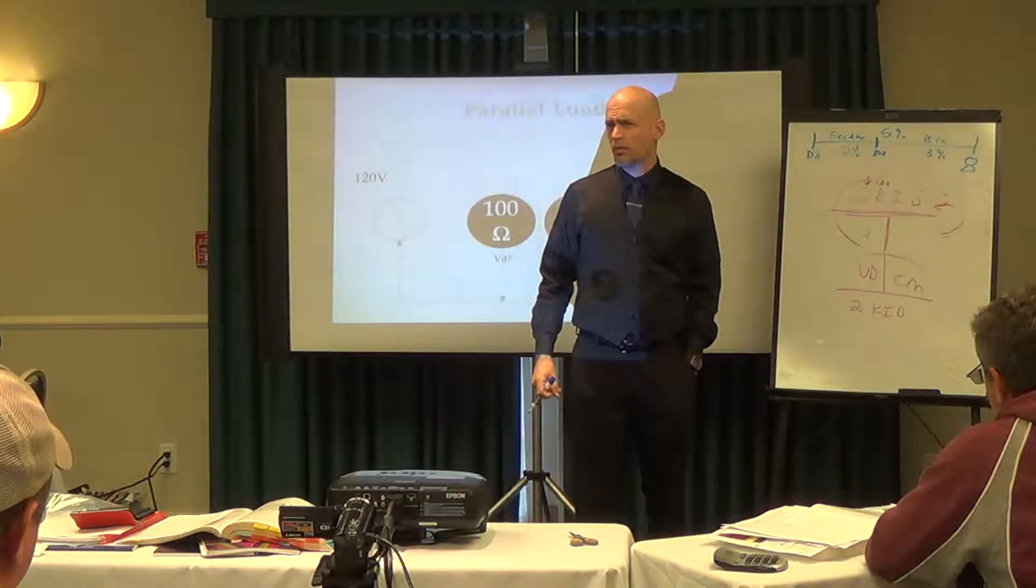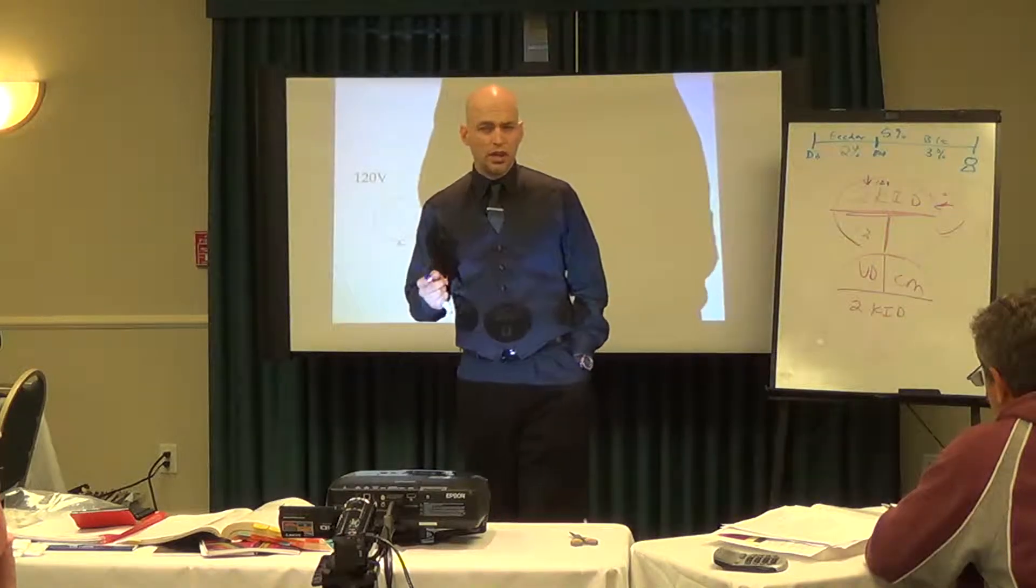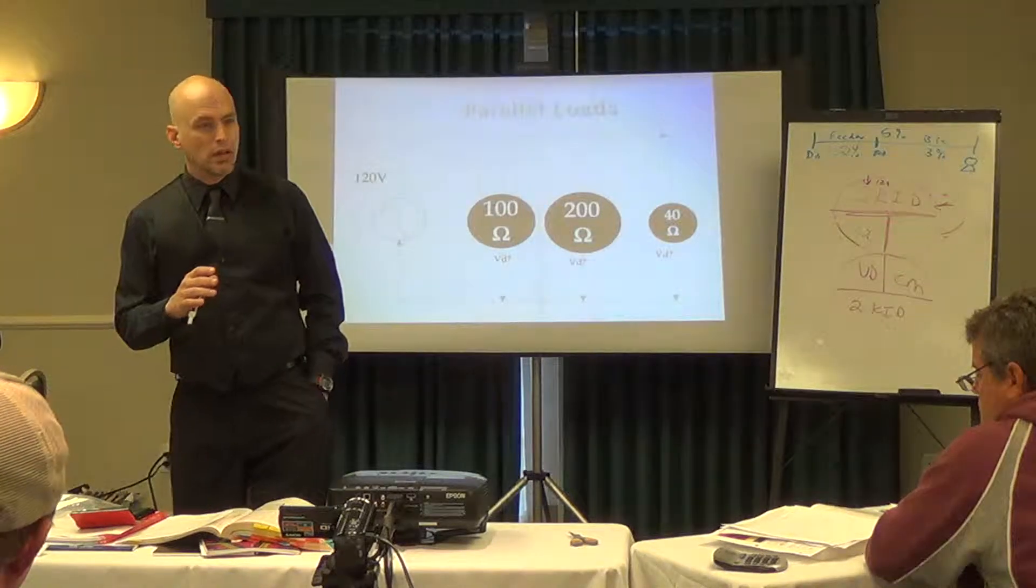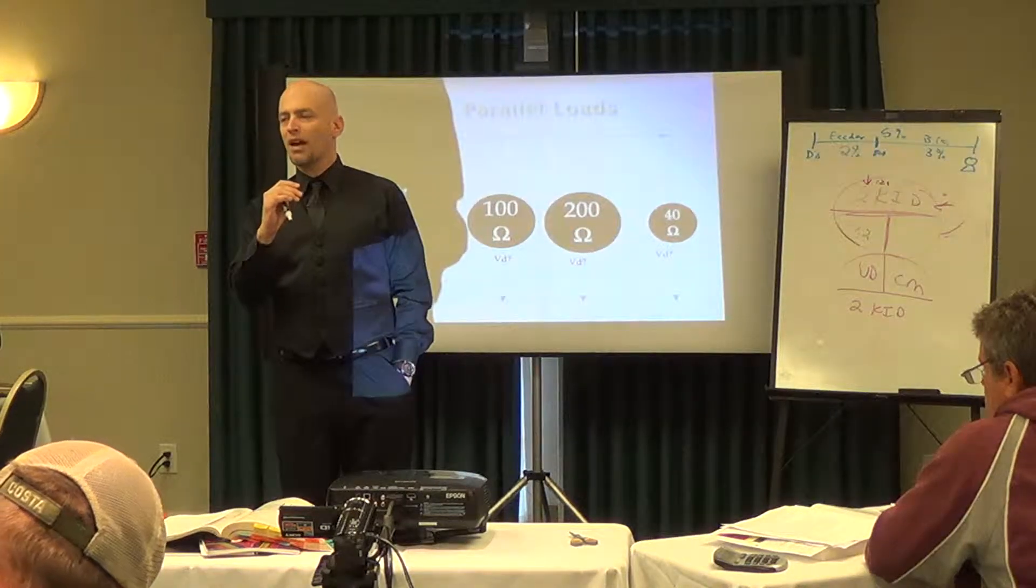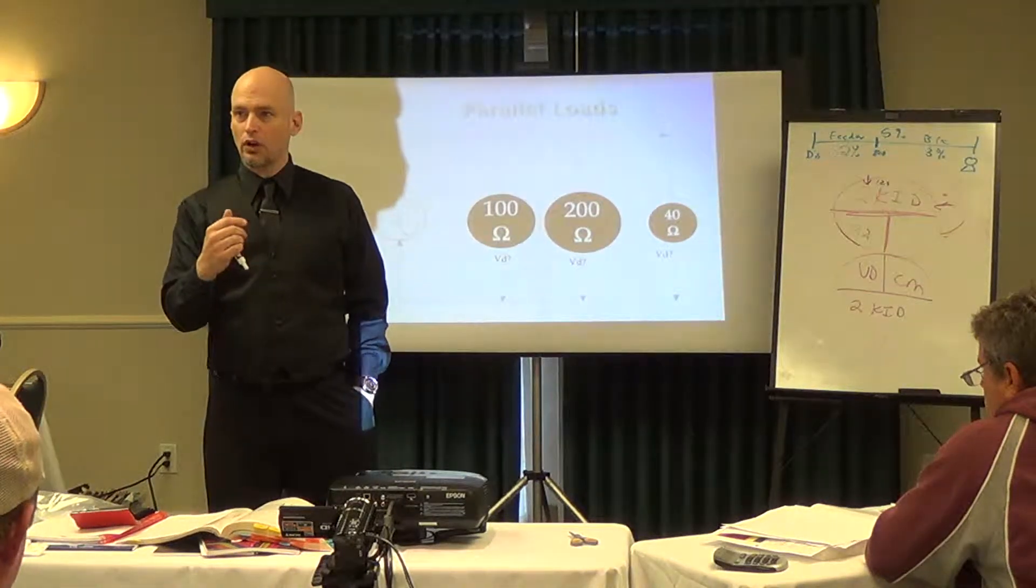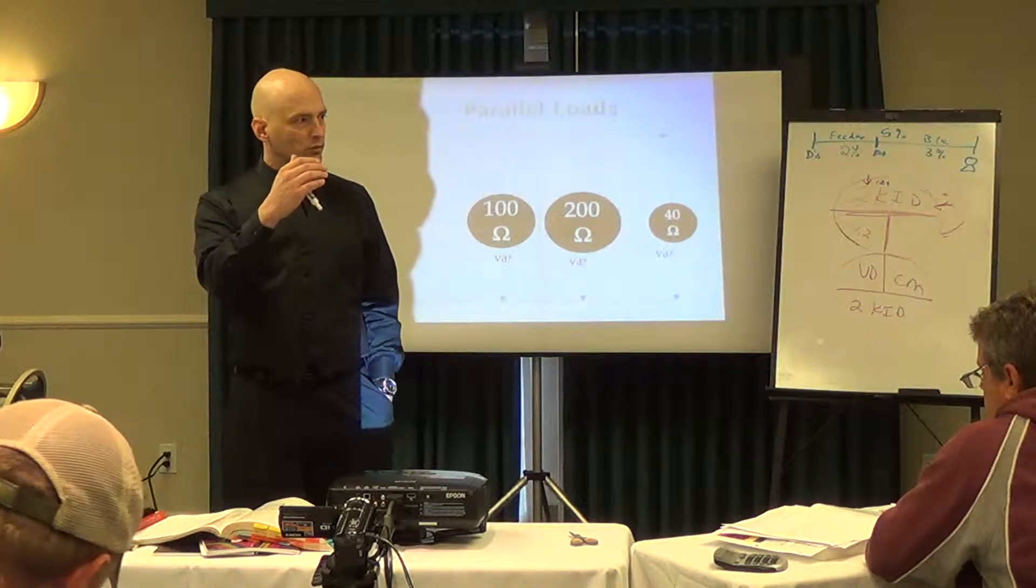What did we talk about yesterday on continuous duty? What's the definition of continuous duty? More than three hours. And so they're telling you there in the question that it runs three to four hours of the period of time that it continues due to load. The reason why this is important to us is because wire has resistance. The higher the current flow in that wire, the higher the resistance value becomes, the more amount of heat that it produces because of that resistance value. And the additional heat load or additional thermal impact will cause an additional resistive value to start increasing in that wire.